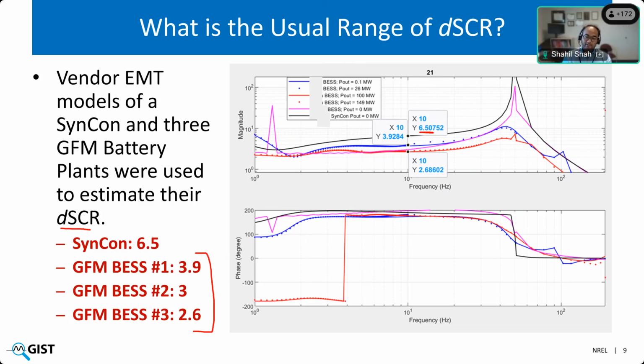So you did that if you understand time domain tests, this is just looking at the same response in a different frame of reference, which gives much more clarity and flexibility in defining specifications. When I say flexibility, what I mean is the Q by V scans or P by theta scans, or for that matter, any frequency scan is independent of the grid condition. Like the time domain response would change depending on what SCR you are using, but the frequency scan would stay the same if you do it properly.